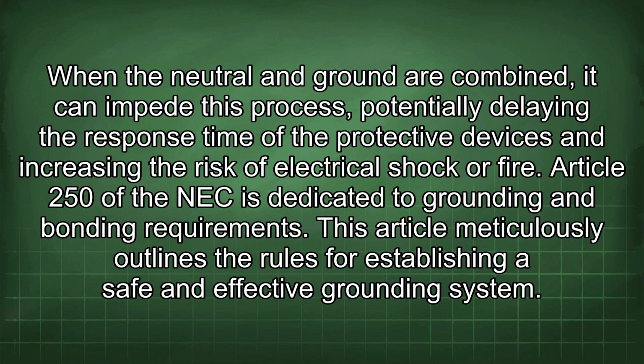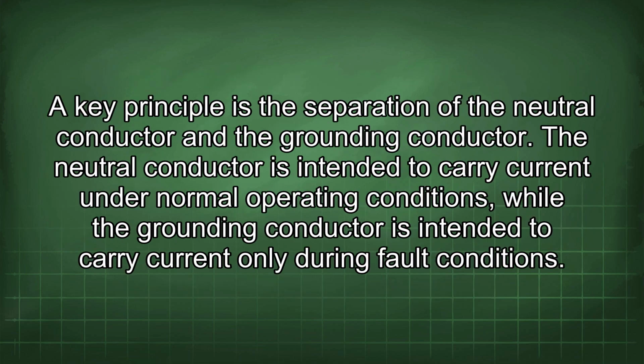Article 250 of the NEC is dedicated to grounding and bonding requirements. This article meticulously outlines the rules for establishing a safe and effective grounding system. A key principle is the separation of the neutral conductor and the grounding conductor. The neutral conductor is intended to carry current under normal operating conditions, while the grounding conductor is intended to carry current only during fault conditions.